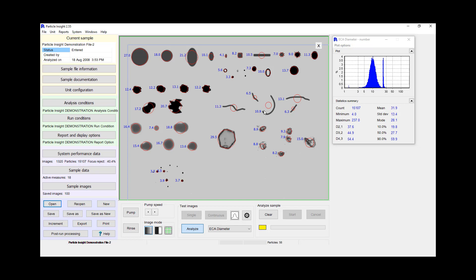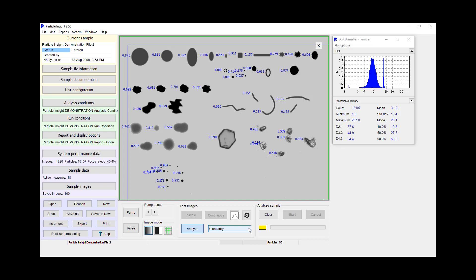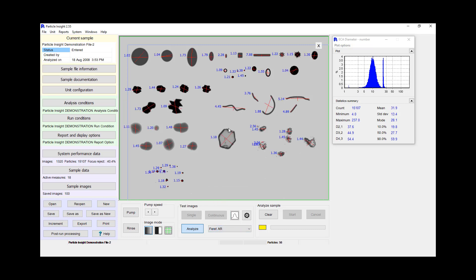But if you assume that they're round and they're not, that's where you can get some interesting results. So assuming this particle is a 10-micron particle and these are 12-micron particles — obviously very different particles will behave very differently. That's where the assumption of sphericity really goes away. When you have irregular particles, it's important to actually characterize them not only by size but also by shape — for example, circularity, how round the particles are, how smooth the particles are, and the aspect ratio of the particles. There is a large number of measurement parameters that we can use through shape analysis because we're capturing the images.